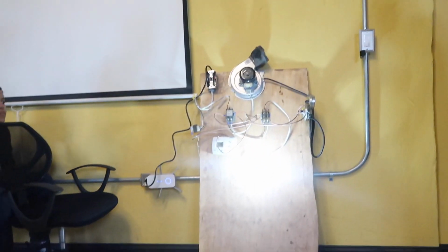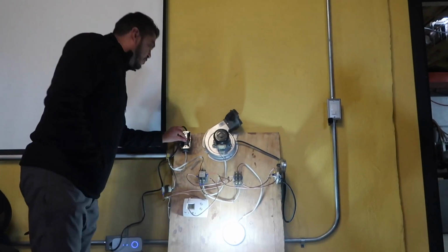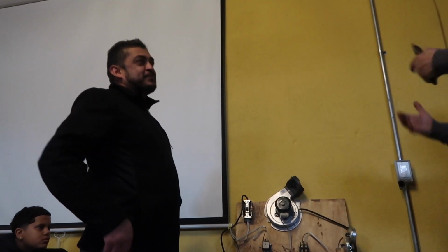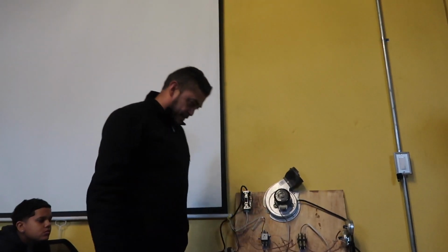Nice. So here, wait like 15 minutes. So here we go, guys. Real quick, this is what it's supposed to do. The thermostat's calling for heat. Turn the thermostat off. No, leave it. You should have just left it like that so you could show them step by step. So the thermostat's going to call for heat.